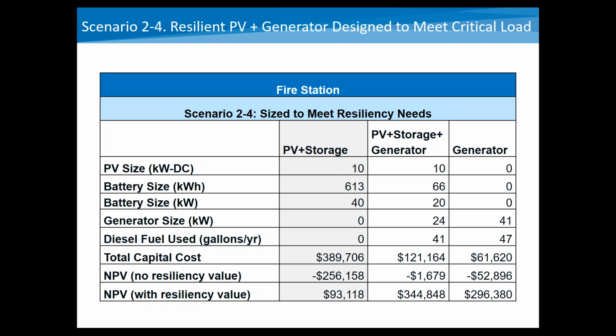In the next column there, we look at PV, storage, and a generator. In this case, we're pairing a resilient PV system with a generator, and so a smaller battery is required because the generator can pick up a lot of the extra load. And so we have a lower capital cost and a much less negative net present value. You'll see it's only negative $1,679, even when you don't include a resiliency value. And when you do include a resiliency value, it's very positive.